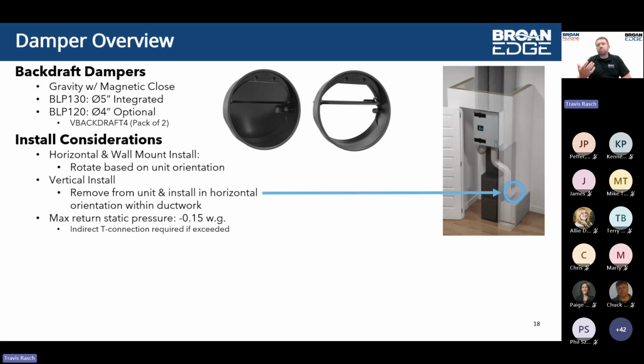Some considerations. I mentioned before, we've got to make sure gravity's our friend. Got to make sure that damper falls and stays closed when we want it to. So when we talk about that horizontal, that wall mount, again, door up, door down, or on the wall, you have the ability to rotate those dampers to the right orientation so that damper falls the way we want it to.